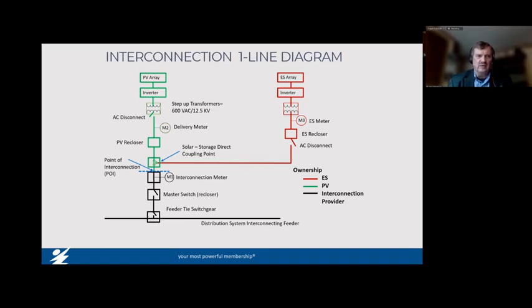Then we go through a photovoltaic recloser. It's basically a big circuit breaker that sits on the ground. And that circuit breaker can trip if there's a problem, or it can be opened up to isolate the solar from the rest of the system. Connexus Energy has permissions and capability to trip that recloser open if we need. And then when it's okay for it to be closed, then ENGIE has the capability to reclose it and put the system back in service.